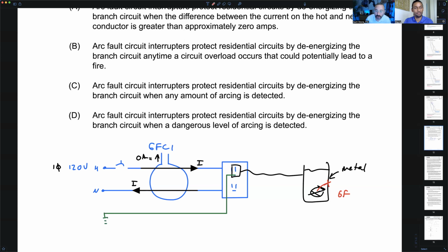Now I've got current that's going to go through the wire, but it's going to come down this way. Here's my ground fault current. Do I have any neutral current left if it's coming back this way instead of on my neutral? No, everything's just shunted to ground. Beautiful. Now this is like short circuit current feeding at our ground fault point and then coming back on the grounding conductor. Am I still going to have 0 amps on the GFCI current sensor? No, you've got a differential that's no longer zero.